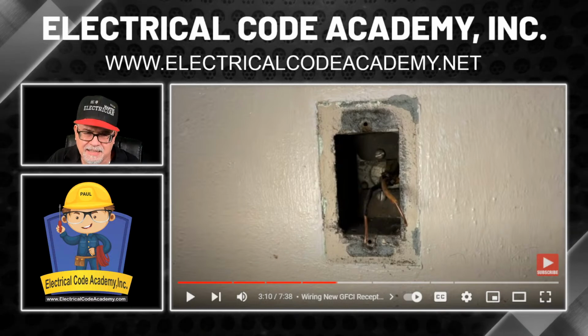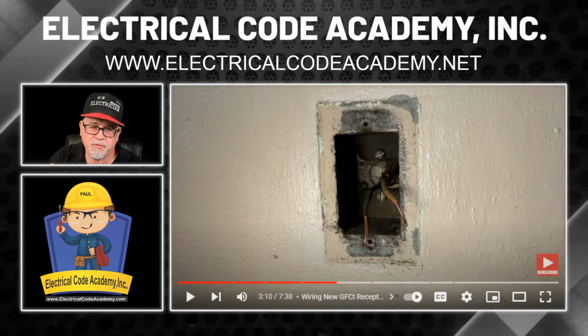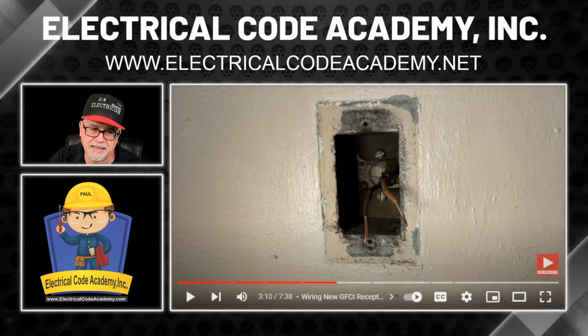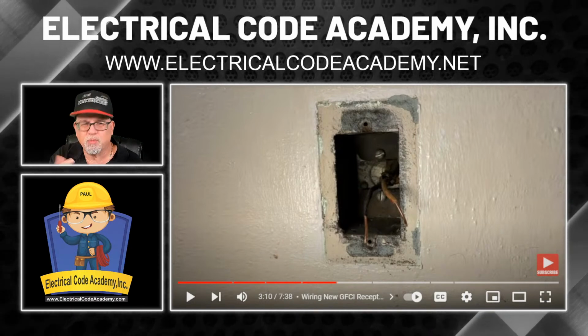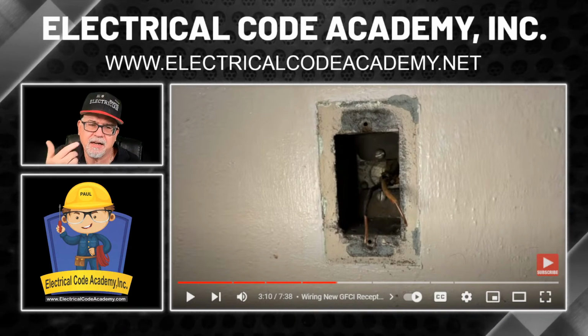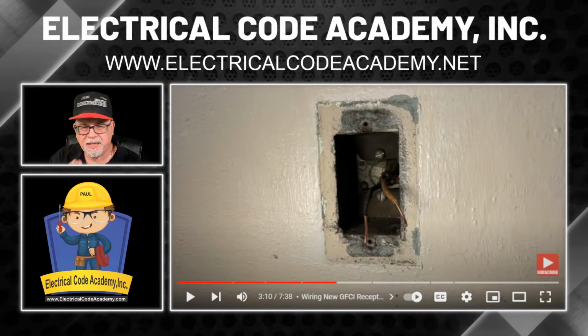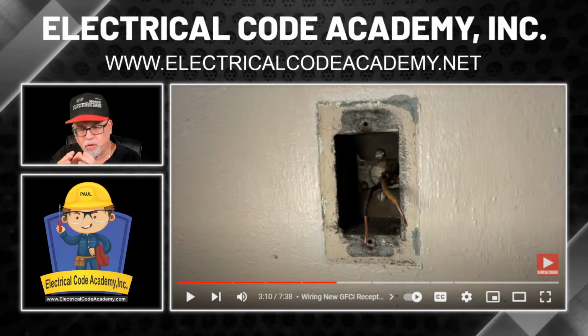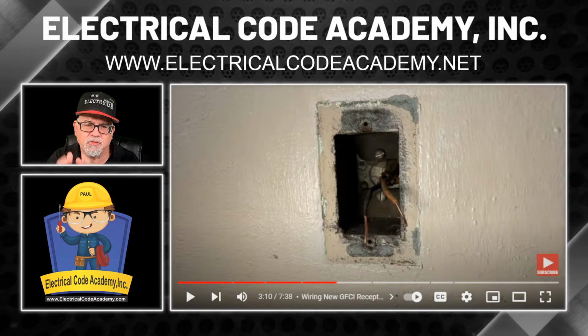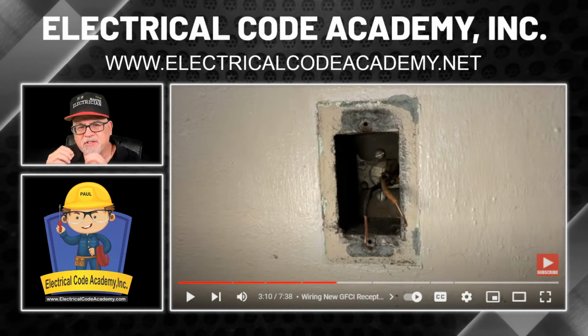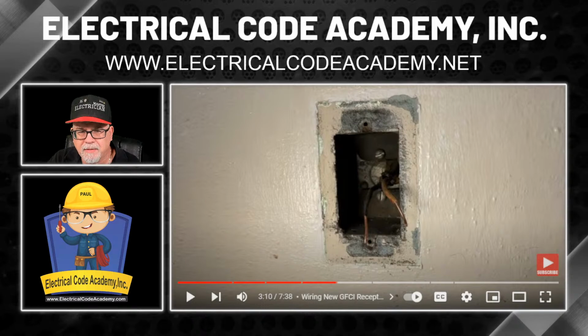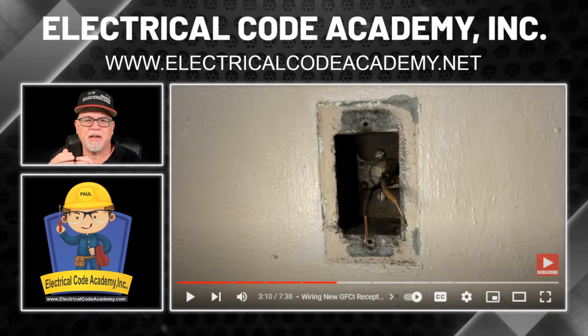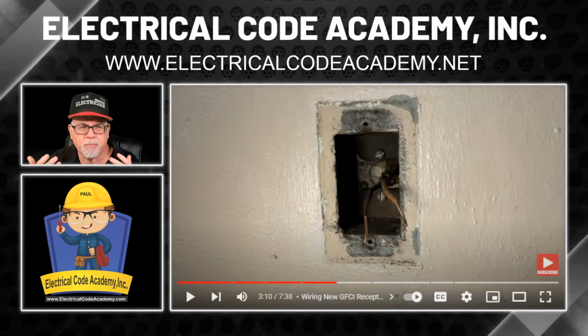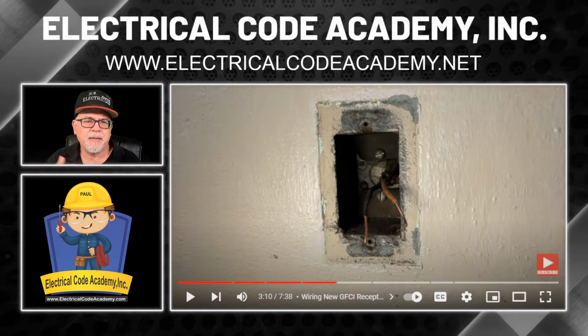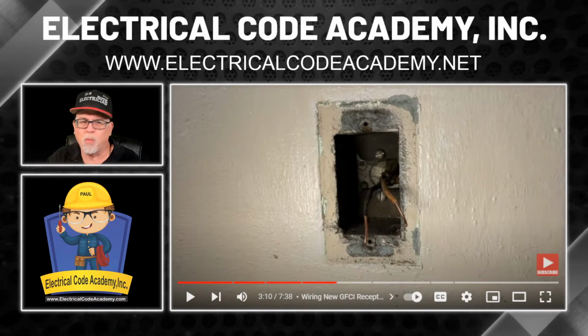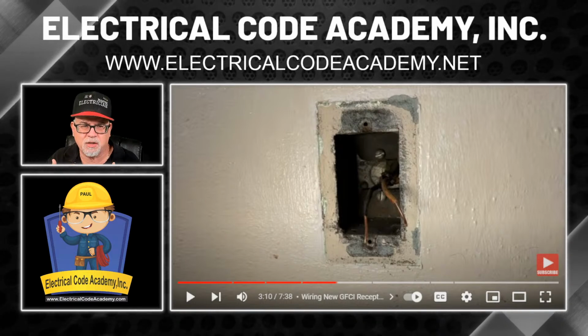One of the things that I like to do, if I were to cut off the receptacle like that, or if the ends were too damaged and I wanted to replace it, is splice on pigtails so that I could take that older, probably a cloth type of insulation, really old, and train that back into the back of the box. That way I'm not tugging and pulling on any of that cloth or whatever. It's probably brittle or could crack off. For me, I want to have less stress on that. I don't want problems that an electrician has to come back and deal with.